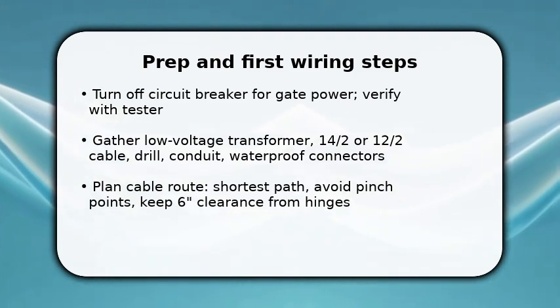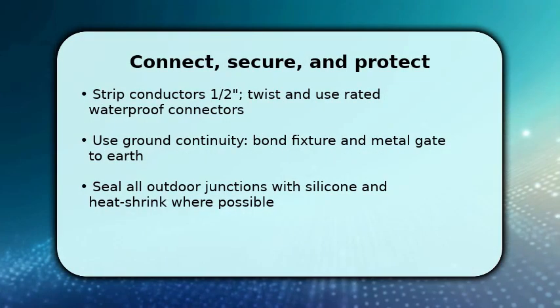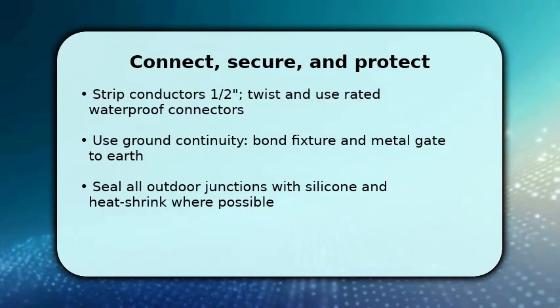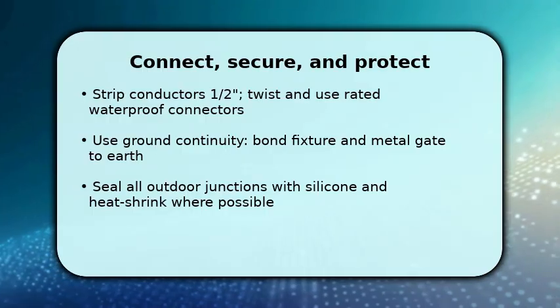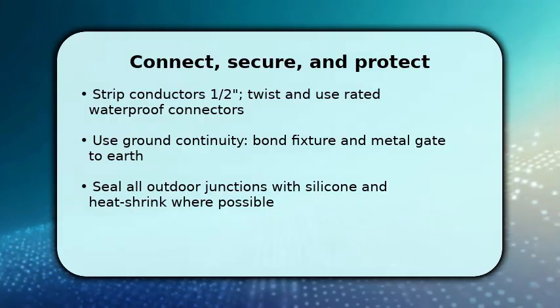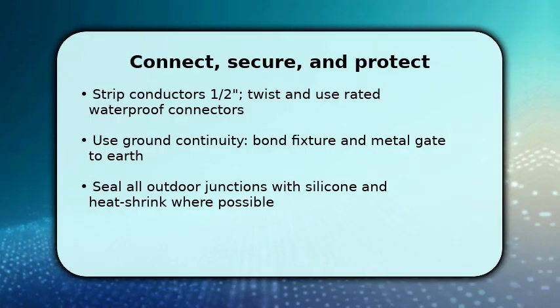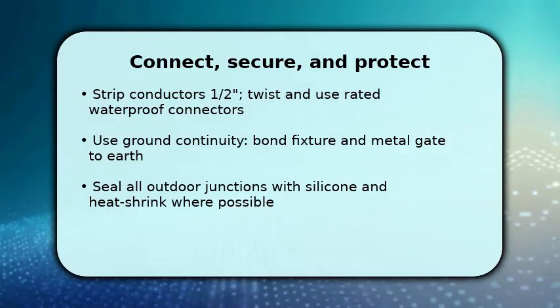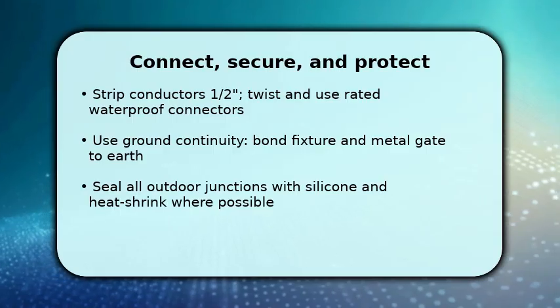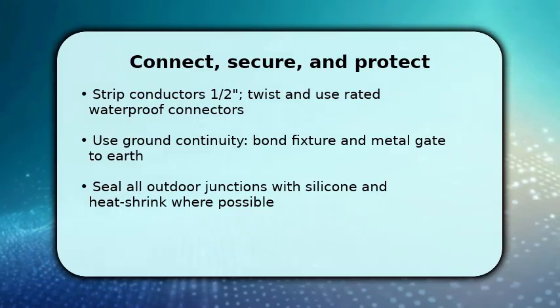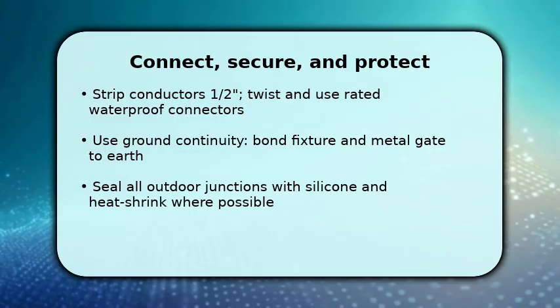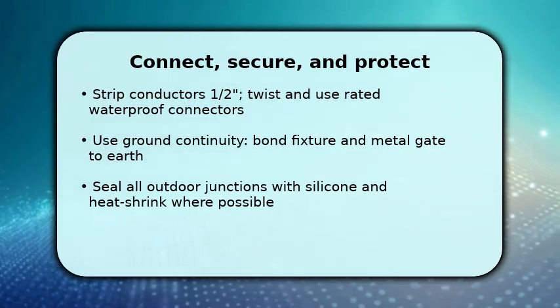You do these steps to prevent shorts and ensure reliability. Now make the electrical connections. Strip 1/2 inch of insulation, twist like conductors together, and use rated waterproof wire nuts or gel-filled connectors so moisture cannot intrude. Then bond the fixture and the gate frame to the ground conductor to prevent stray voltages. This protects you and the electronics.